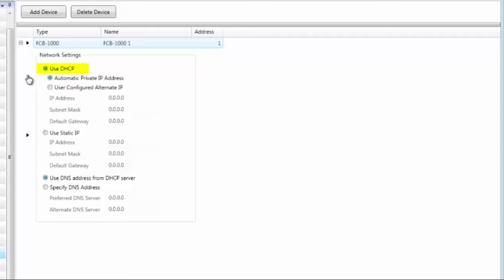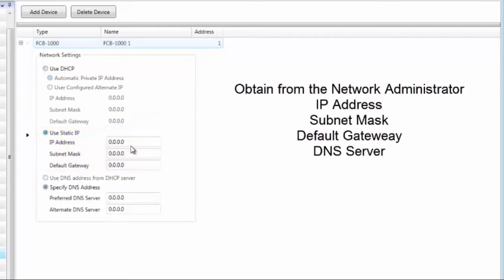By default, the FCB-1000 is set to DHCP — Dynamic Host Configuration Protocol — which means the Ethernet connection will automatically try to obtain an IP address from the connected network. If that network has a DHCP server, it will likely get an IP address, though you may need to consult the network administrator to ensure it has access to both the building network and the internet. If the network administrator prefers to assign a static IP, select Static IP and obtain from them an IP address, subnet mask, default gateway, and DNS server.